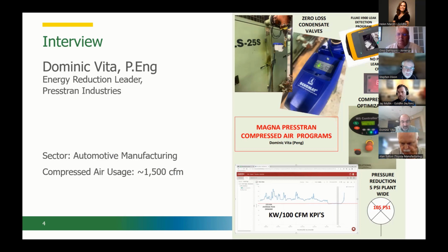Because right now you run 2 of the 3 compressors at a time. One of them has a VFD, and you're using cascading pressure bands to control when they come on. Is that correct? It's about 7 psi. Yeah. The variable has 3 different set points. It has a kick on to run to about 105 psi. Then it'll try to optimize and keep at 100, and then after it holds that for a while, after 10 minutes it drops down to a lower trigger set point.